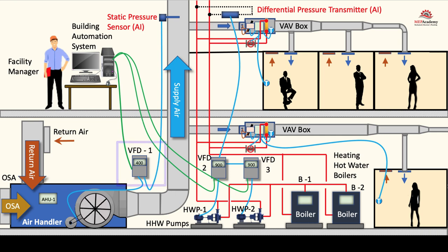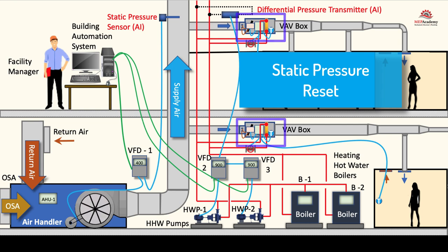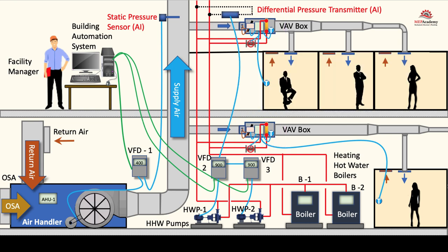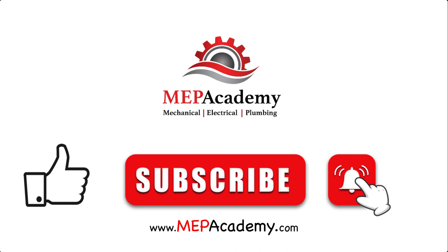There is a variation of the fixed static pressure set point strategy that uses resetting of the static pressure set point based on the feedback of terminal damper positions. By utilizing a static pressure sensor in conjunction with fan control systems, HVAC systems can maintain the desired static pressure levels or reset levels, optimize airflow, and ensure efficient operation. This control mechanism helps balance air distribution, control temperature differentials, and improve energy efficiency in HVAC applications. If you liked this video, please give it a thumbs up and subscribe to our channel. Thank you.